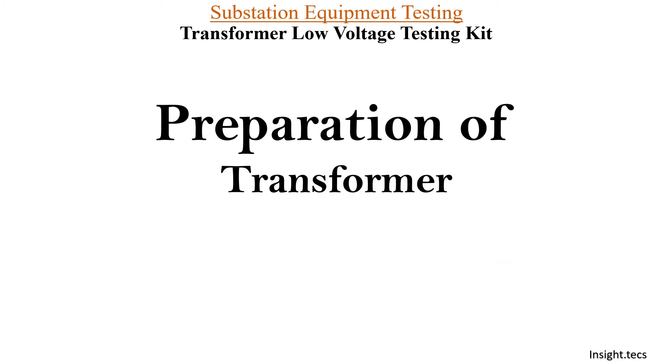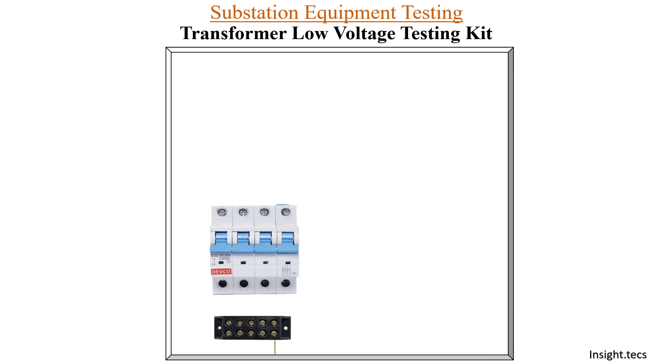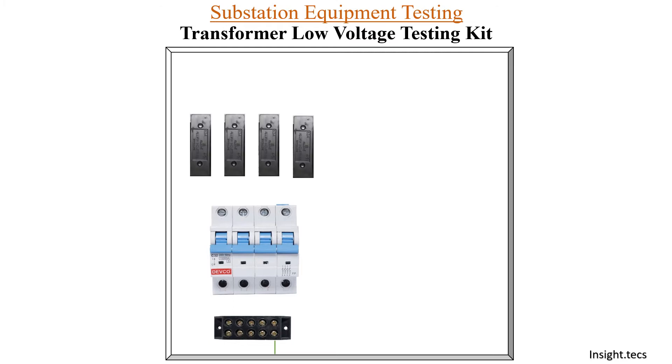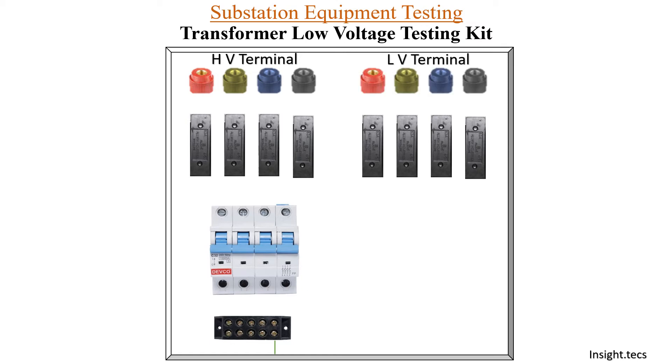Now let us see the preparation of the transformer low voltage testing kit. For making this kit, you will require a plain board of this size. You will connect a terminal block at one end of this board, then MCB is connected, then four fuses are connected. Four fuses are placed for the HV side and four fuses are placed for the LV side. On the fuses, you connect the terminal blocks for HV terminals and similarly for LV terminals. This is the basic general arrangement that you need to do on the board.